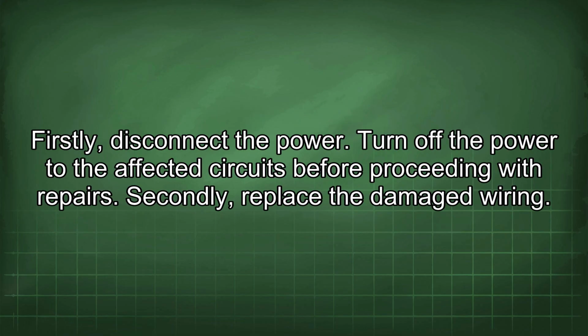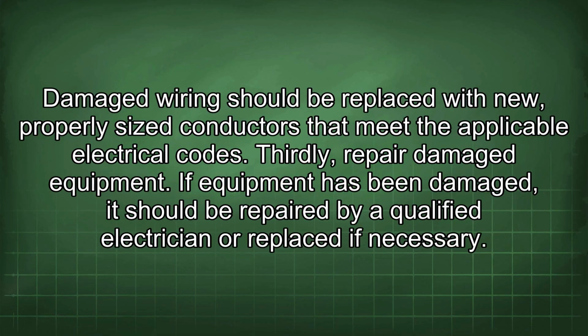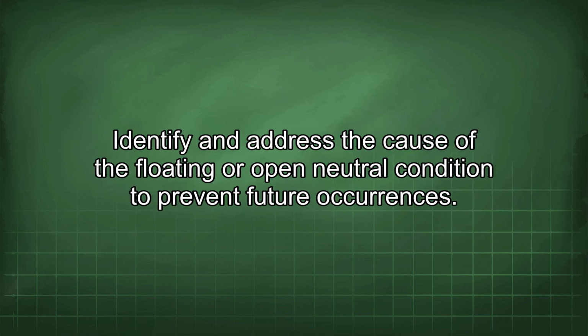Firstly, disconnect the power. Turn off the power to the affected circuits before proceeding with repairs. Secondly, replace the damaged wiring. Damaged wiring should be replaced with new, properly sized conductors that meet the applicable electrical codes. Thirdly, repair damaged equipment. If equipment has been damaged, it should be repaired by a qualified electrician or replaced if necessary. Identify and address the cause of the floating or open neutral condition to prevent future occurrences.